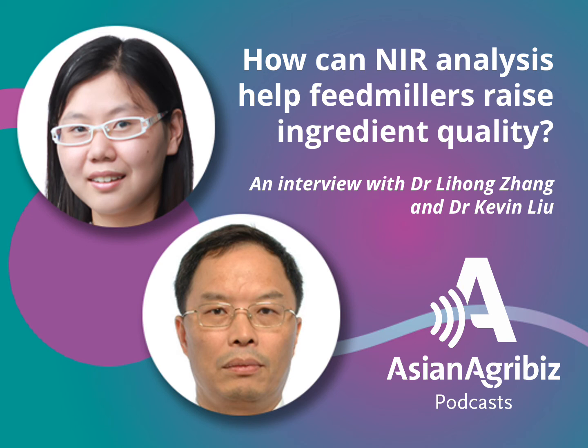You mentioned that if a calibration set is based on a corn soybean meal-based diet, we cannot apply it to a wheat soybean meal-based diet. So that means the calibration set for each sample is different. Yes. NIR measures vibration of organic compounds, and the composition of grain differs significantly in terms of chemistry and NIR absorption. Therefore, the calibration set for each feed ingredient is unique.